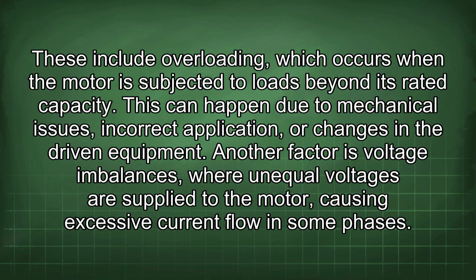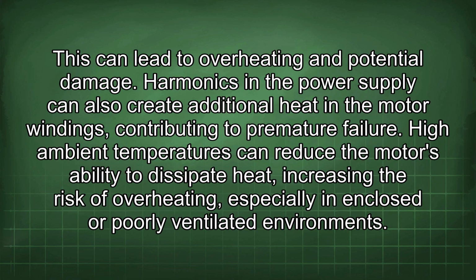These include overloading, which occurs when the motor is subjected to loads beyond its rated capacity. This can happen due to mechanical issues, incorrect application, or changes in the driven equipment. Another factor is voltage imbalances, where unequal voltages are supplied to the motor, causing excessive current flow in some phases. This can lead to overheating and potential damage. Harmonics in the power supply can also create additional heat in the motor windings, contributing to premature failure.